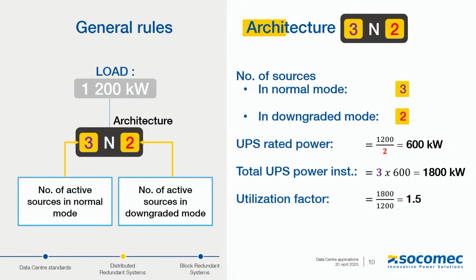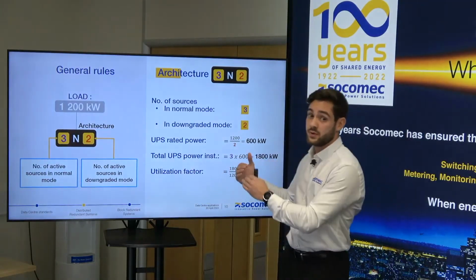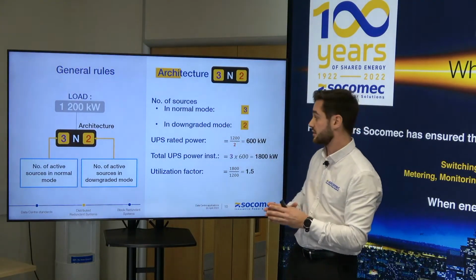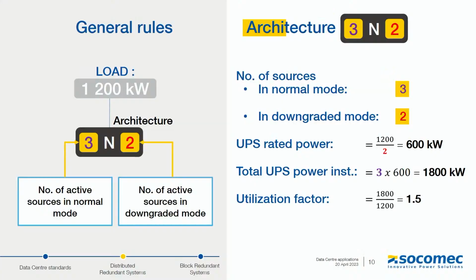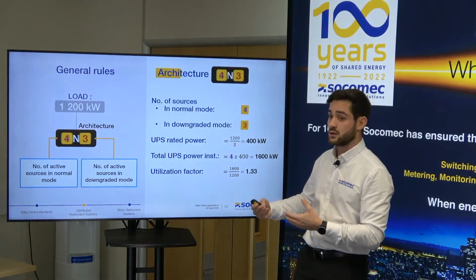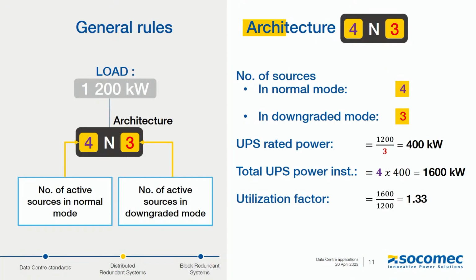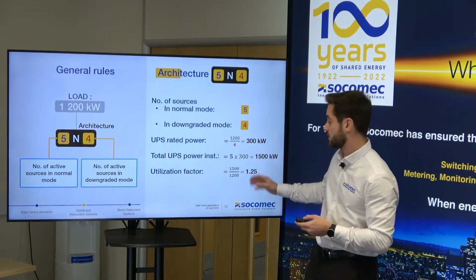So if we move now to the 3N2, exactly the same math, the same calculation. But as you can see here, just by increasing the number of systems in normal mode and in downgraded mode, we are able to reduce the UPS power installed. We now moved from 2.4 megawatts to 1.8 megawatts, which can reduce the cost for the installation, but of course for the UPS system, the batteries, etc. If we go a little bit further, we've got the 4N3 system, exactly the same principle, and with this solution we are able to reduce down to 1.6 megawatts. And then the last example here, the 5N4 system, which again reduces the whole installation, and in this specific case we are moving down to 1.5 megawatts.